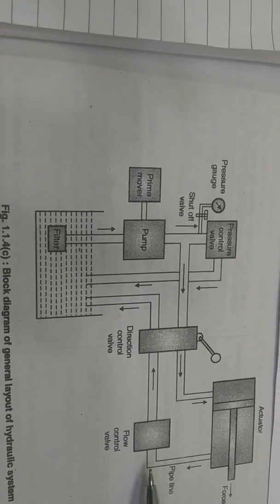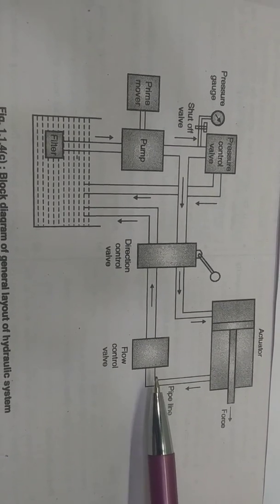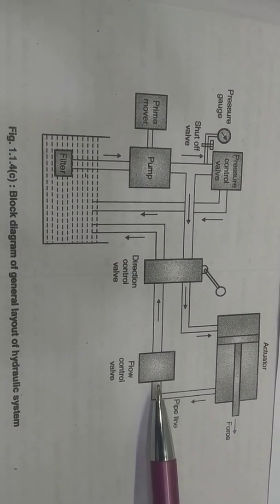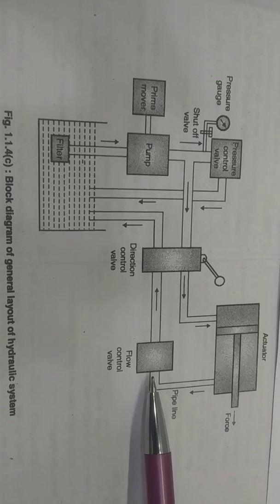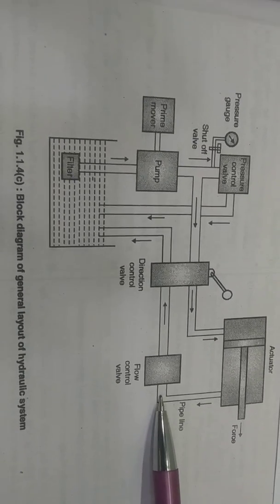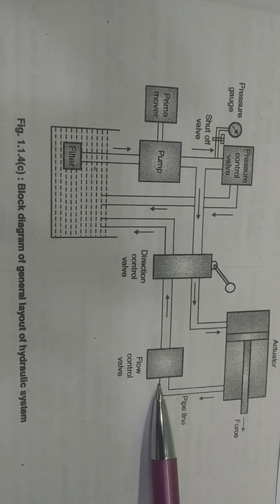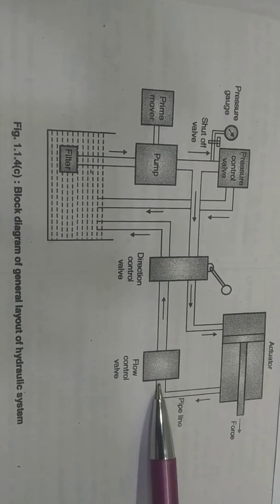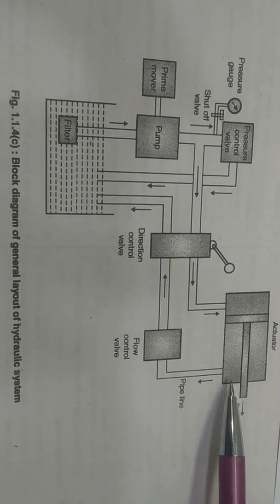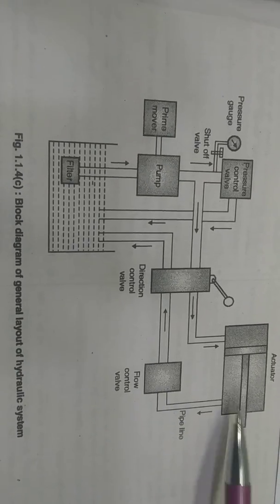The next component is the flow control valve. There are different types of flow control valve. The main function of the flow control valve is to regulate the flow rate of the oil. When we regulate the flow rate, we can obtain different speeds of the actuator by operating the flow control valve.